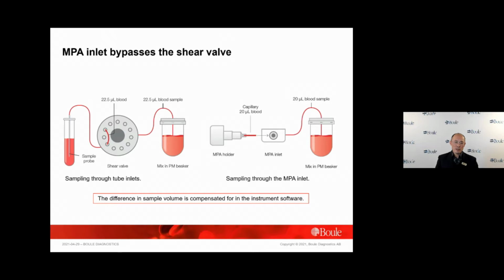And as Annette mentioned and also emphasized, this is a very good feature, but it also depends on the correct operation by the user, to make sure only the microcapillary tube contains blood. No air bubble inside, no excessive blood on the outside wall. So the operator should check if there is any air bubble inside the tube and wipe away the excessive blood from the outside with a tissue paper. In this way, the precision of the MPA inlet can provide a very reliable result.